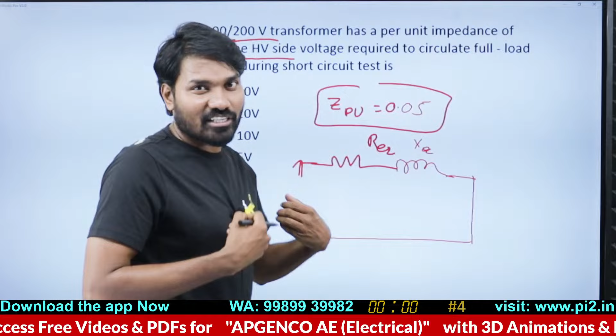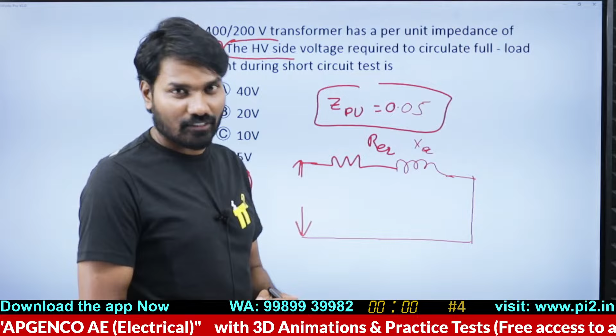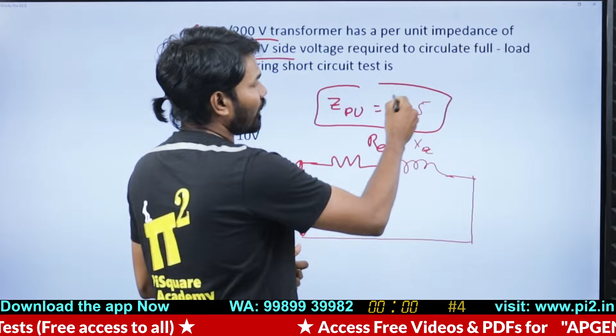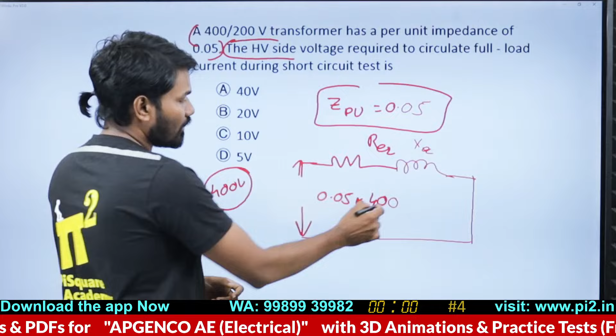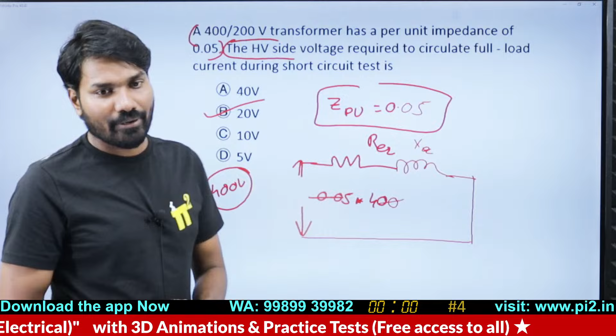If you give 400 volts here in the short circuit condition, boom - big blast of the transformer. So you cannot give full voltage, you should give a reduced voltage. Now how much is the reduced voltage to allow the rated current? That is equal to this per unit voltage with respect to rated voltage - simply 0.05 per unit into rated voltage. 400 - the zeros and these two decimals cancel - 5 into 4 is 20 volts. Answer is B. Simple, simple.